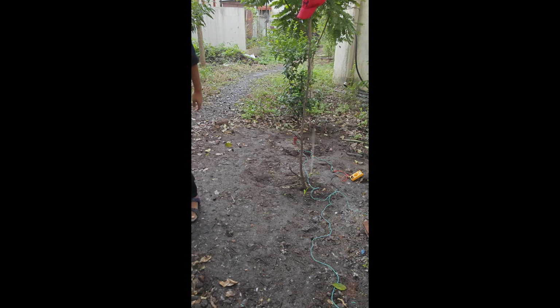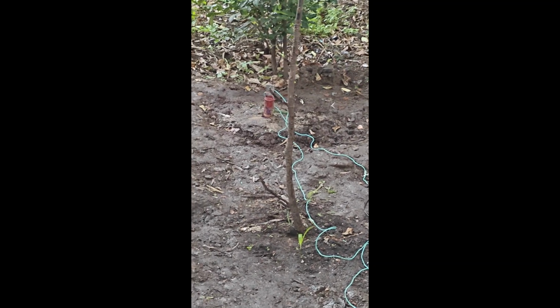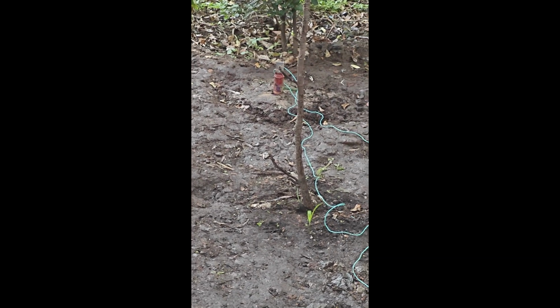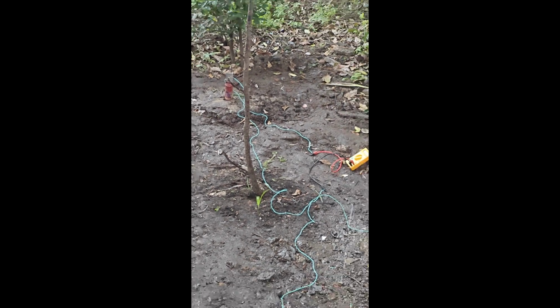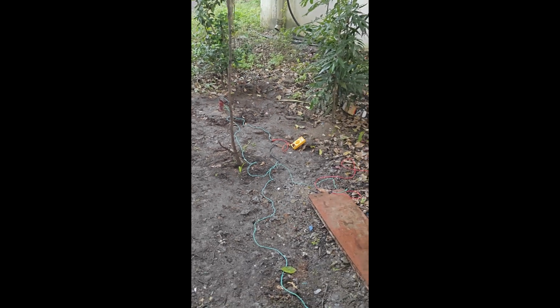From this resistance we will subtract the resistance of the auxiliary rod and current rod. We are also subtracting the resistance of the earthing rod, and then we get the exact value of earth resistance. All this data will be provided to the maintenance team continuously using this fall of potential method.